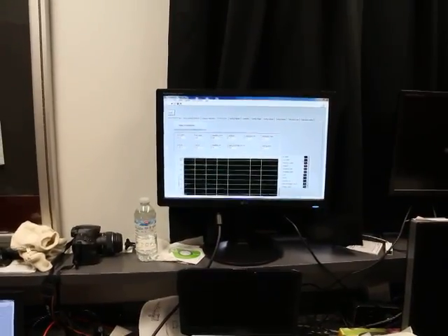We have cooling water, which is also not so important because it will heat up because the pump is not running. We have in air. This is the second sensor. This is not connected, so it will show a value which is garbage. This is out air, which is 34.3. We will see the mass flow air, which is 33.14. And heat exchanger out air makes no sense over here, but this is the one which is at the outlet of the water air heat exchanger, what you would have if you have a closed loop circuit.